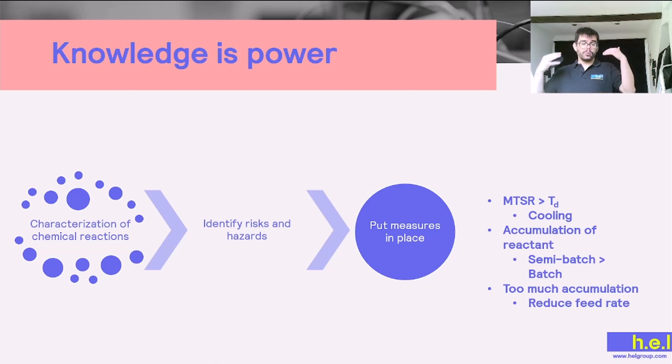Also, it can be the case that we thought that maybe we wanted to add all our reactants into the reactor, and then we observed that no, that's going to generate a huge MTSR, so maybe we want to move from a batch kind of approach to a semi-batch approach in which we are going to slowly feed one of the compounds into the reactor. But it can also be the case that even using this kind of approach, there's going to be too much accumulation of heat, and then what we can do is playing around with the feed rate, and this is what we're going to see on the next slide.